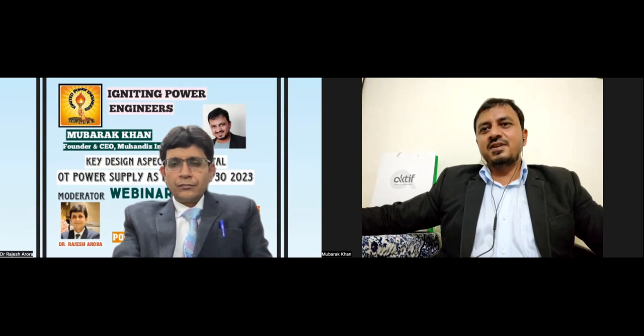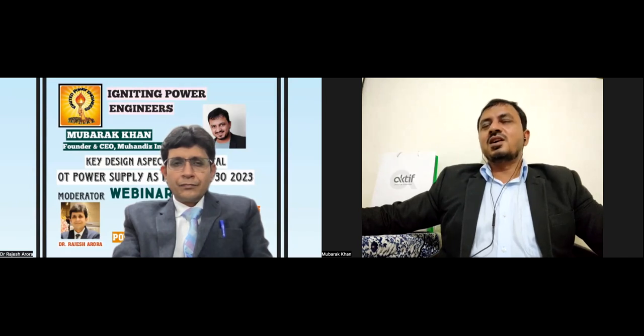If I connect another phase to the earth in the same way, there will be fire without any question. That is why we have an insulation monitoring device and a fault location system to detect the first earth fault and remove it as soon as possible. Under normal operating conditions, there is very low probability that a fault in phase 1 and phase 2 will come together at a time with a very strong direct short circuit.